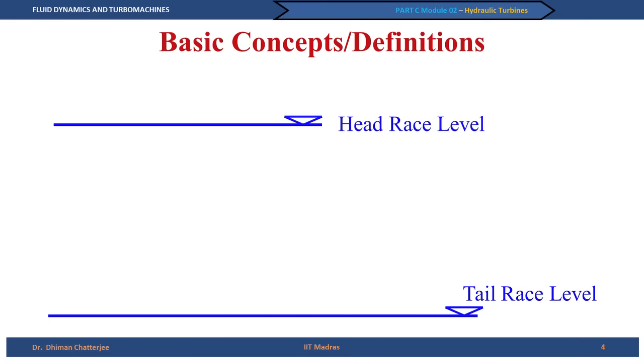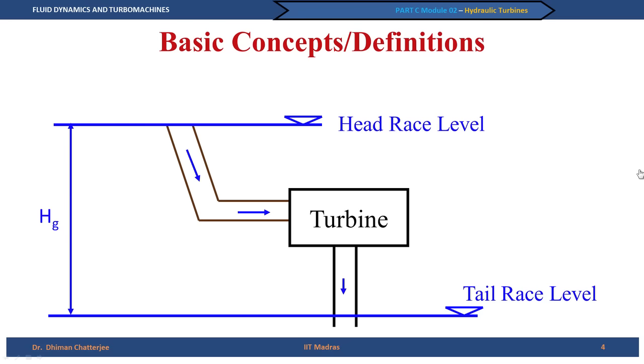We can say there is a headrace level — nothing but the reservoir — and a tailrace level on the downstream side of the turbine. In between, we have a turbine installed with a penstock piping system bringing the water through. The geodetic level difference between the headrace level and the tailrace level is the head available, called the gross head H_G.